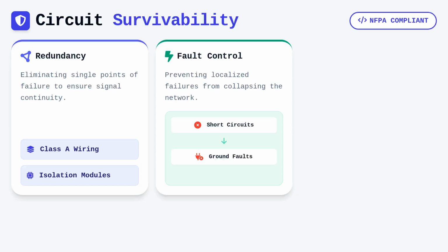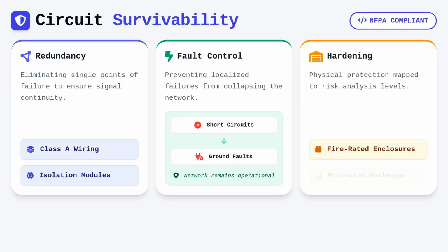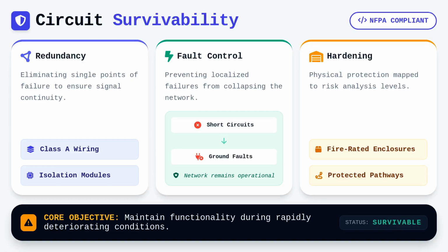We must also consider the physical protection of the cabling itself, ensuring it is routed through fire-rated enclosures or protected pathways that align with the specific hazard levels identified in the building's risk analysis. Designing for survivability means acknowledging that while the system must continue to function, the environmental conditions under which it operates will be rapidly deteriorating.